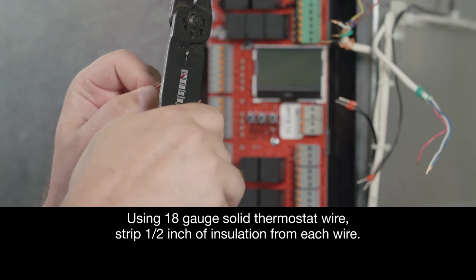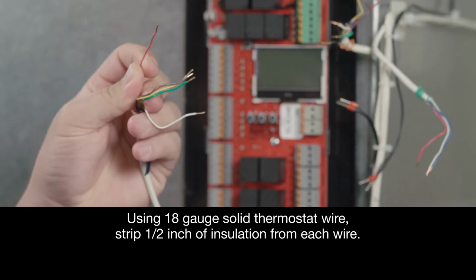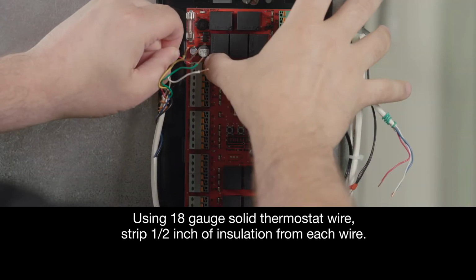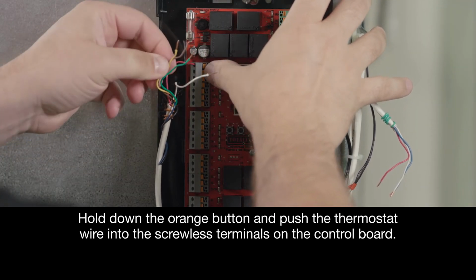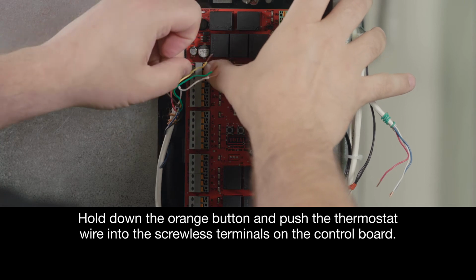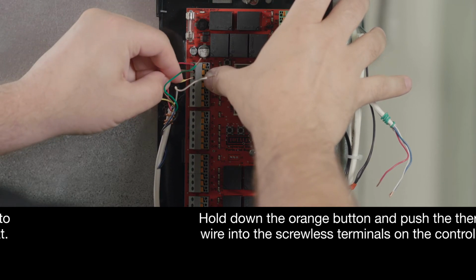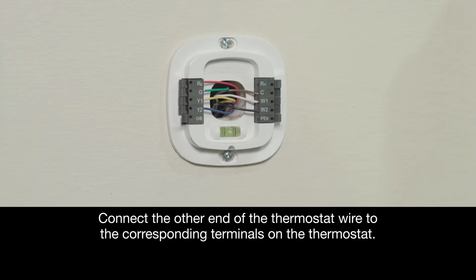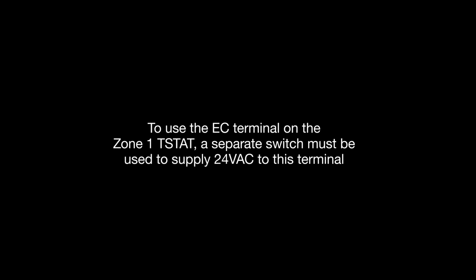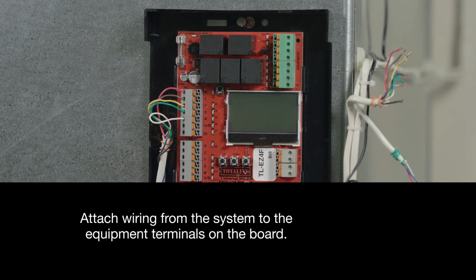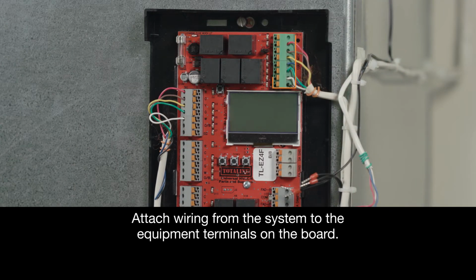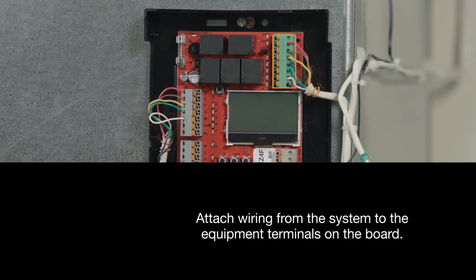Now, using 18-gauge solid thermostat wire, strip a 1/2 inch of insulation from each wire. Hold down the orange button and push the thermostat wire into the screwless terminals on the control board. Then, connect the other end of the thermostat wire to the corresponding terminals on the thermostat. To use the EC terminal on the Zone 1 T-stat, a separate switch must be used to supply 24-volt AC to this terminal. Next, attach wiring from the system to the equipment terminals on the board.